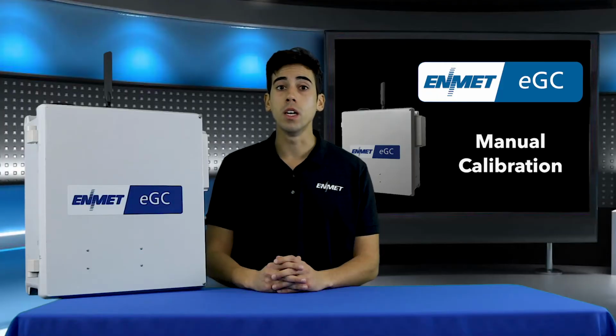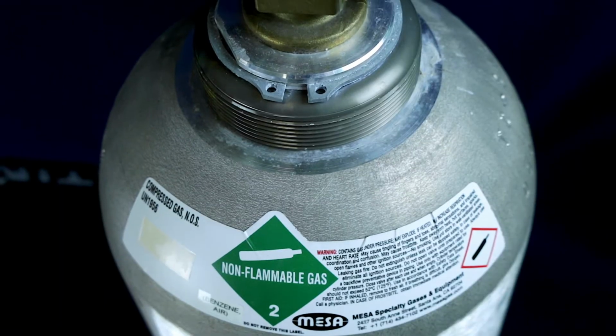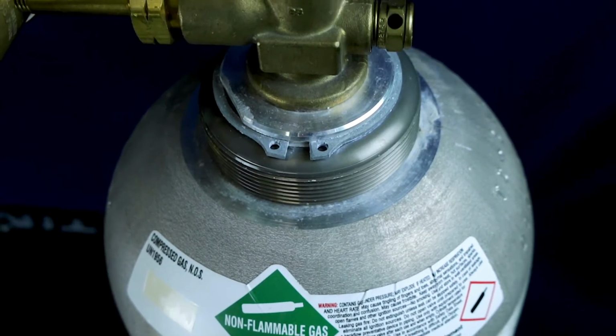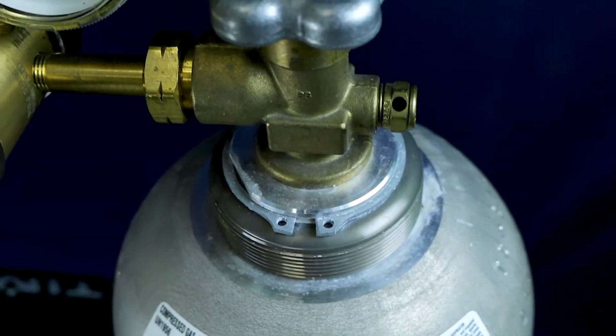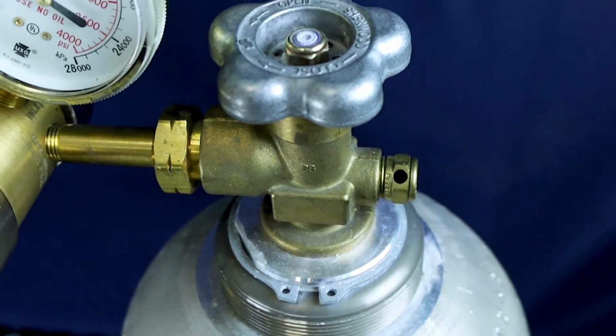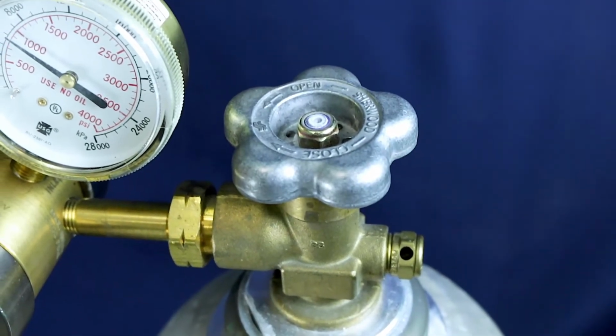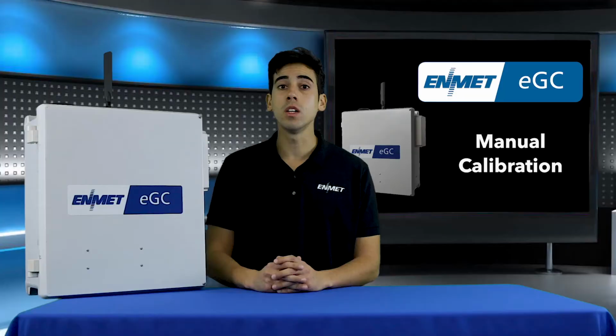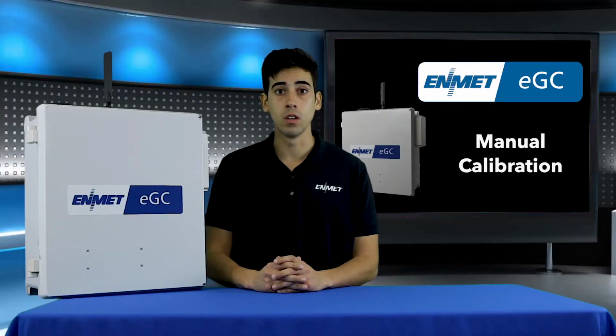The first few readings will be invalid until the instrument has fully warmed up for 30 minutes to reach its operating temperature. Our eGCs are configured to use 10 parts per billion calibration gas standards. Concentrations other than 10 parts per billion will result in incorrect readings by the unit.